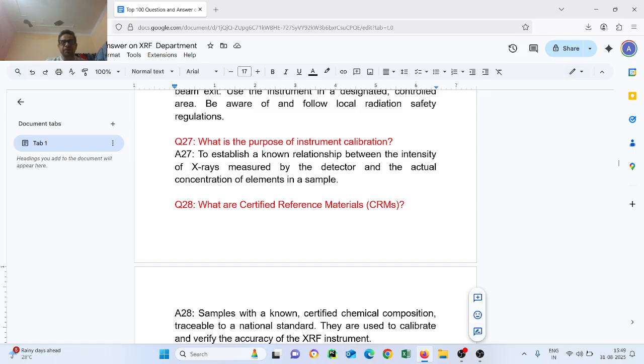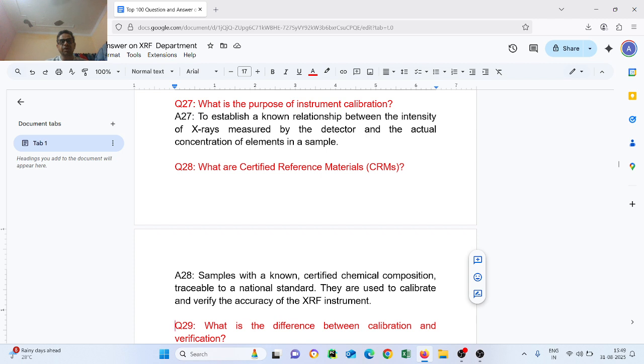Next question, question number 28. What are certified reference materials, CRMs? Samples with a known certified chemical composition traceable to an international standard. They are used to calibrate and verify the accuracy of the XRF instrument.